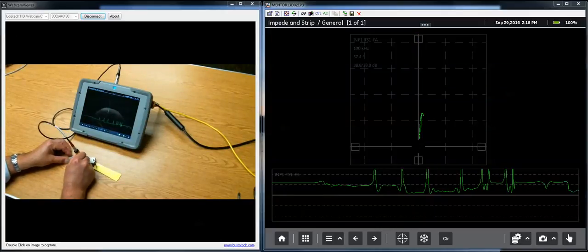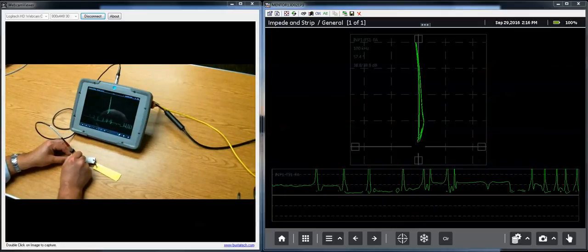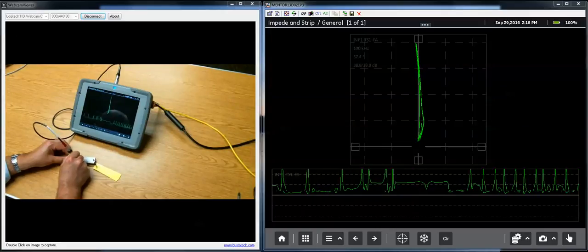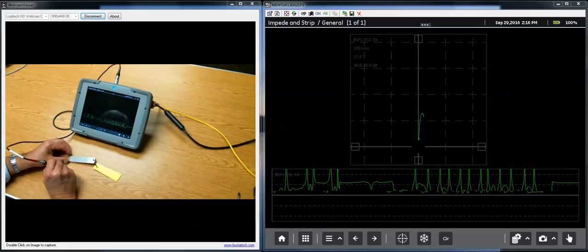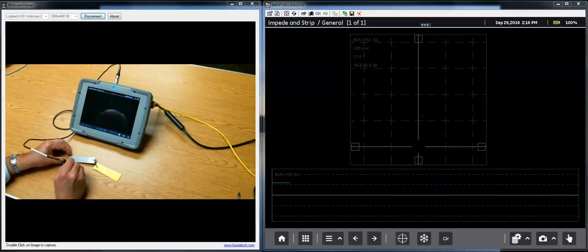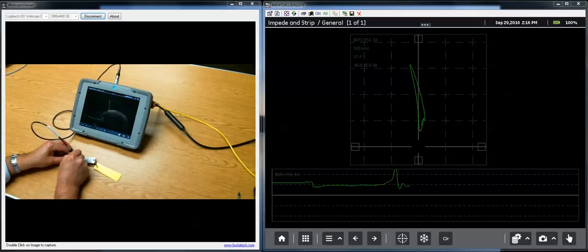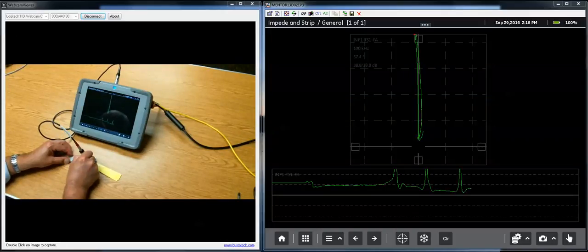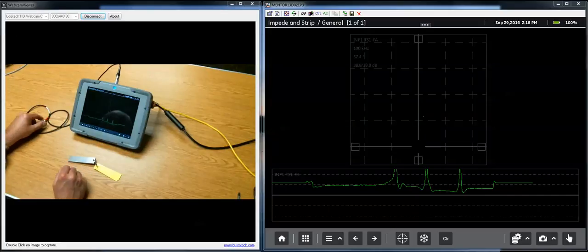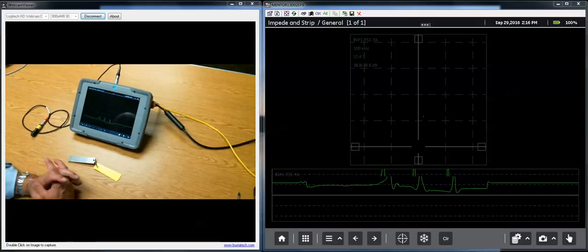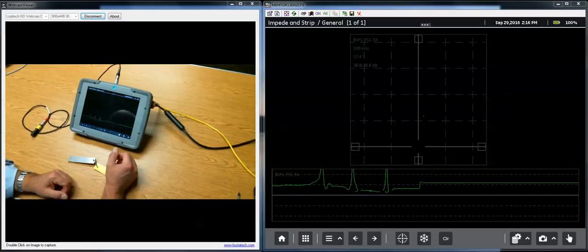I've got it all set up so that my one millimeter deep notch in my standard gives me just about a 100% screen height indication. So if I clear it, I go clean metal, half millimeter, one millimeter, two millimeters. So that's the basics of interacting with the Mentor EM with gestures.